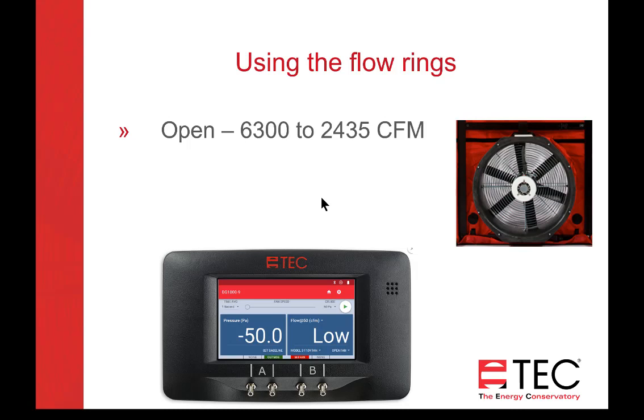And if we're seeing a low on the right side, in this case we've got the house up to 50 pascals and it's reading low on the right. So what's happening is we're out of the range of this fan. We're less than 2435, so our pressure at the flow sensor is too low.